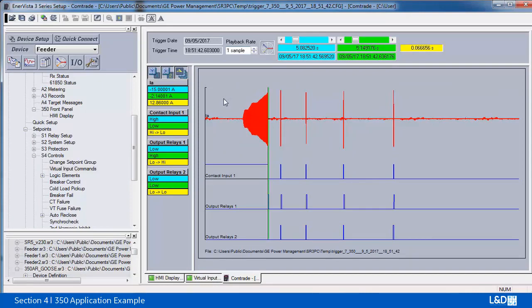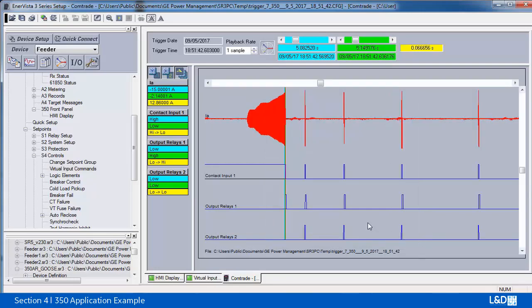is finished, so I can see that the pickup and output of the trip, which is relay 1, we got the AC increased until the 4 shots of the reclose, and relay 2 is the close. We got 4 shots of the reclose. The time between these are the dead time setting of the relay.